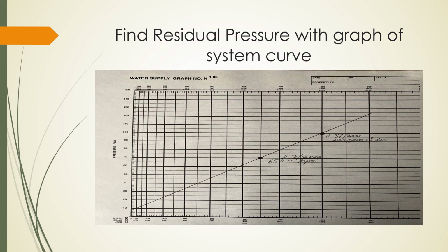You could also do this through calculation. I'm not going to bother with that because this is so simple. You can go to Harold Wass's book that I referenced earlier, Sprinkler Hydraulics, and they've got a series of calculations and equations that will help you do that. But this is so simple that you really don't need to go through that exercise. So basically, we've been able to slide up and down this system curve to extrapolate different densities, demand, and residuals based on a single point.